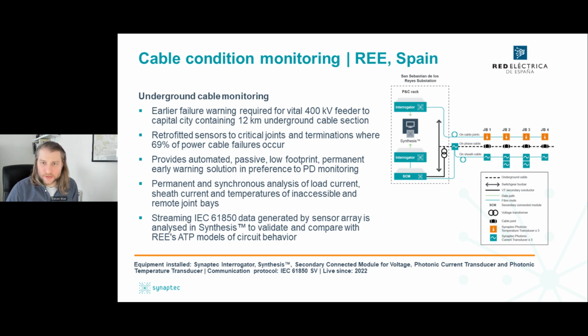But at the moment, that's really the only solution: people need to walk the distance of the cable and inspect the terminations and joints. And we know that those cable terminations and joints are often the source of failures. So the sensor system that we've deployed is monitoring phase currents, sheath currents, and the joint temperatures, and that's distributed along the length of the whole cable. So this is a very good fit for passive sensing, where we can install the sensors once, but for the lifetime of the system, we get streaming measurements from all those locations.